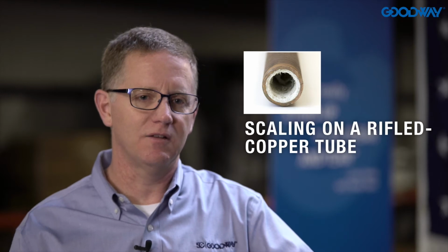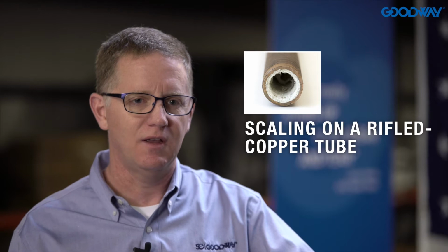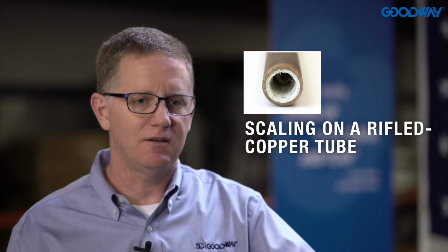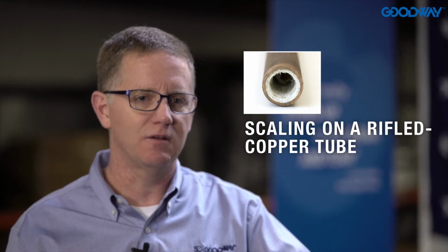Hard water is the biggest contributor to scaling. The more mineral that's within a water source, the more likelihood it is to fall out of suspension. As it falls out of suspension, it plates itself onto the heat transfer surface, not allowing proper cooling or heating.